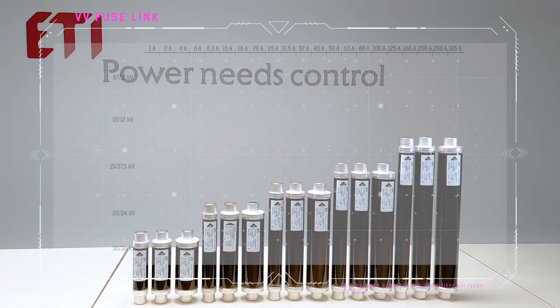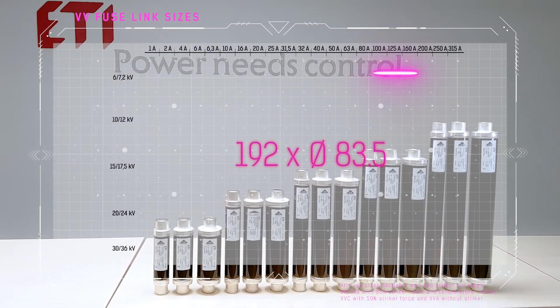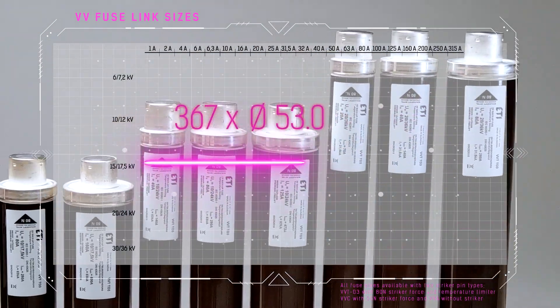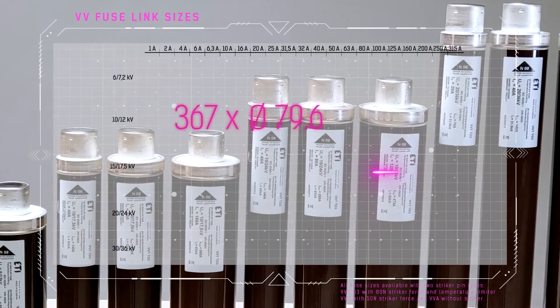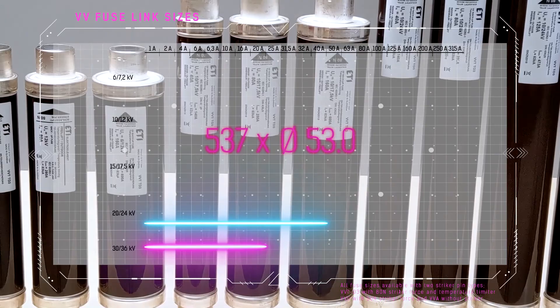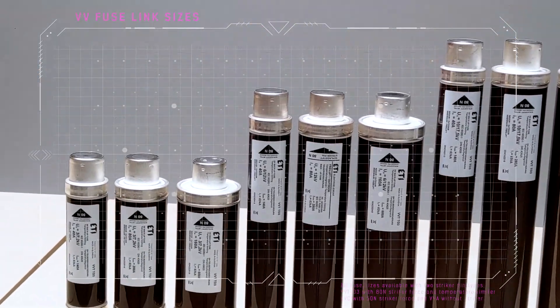ETI's new generation of medium voltage fuses, the VV series, encompasses fuses with various rated voltages and dimensions in standard and non-standard versions. There are two striker pin types: VVT D3 with 80N striker force and temperature limiter, and VVC with 50N striker force, as well as VVA without a striker.